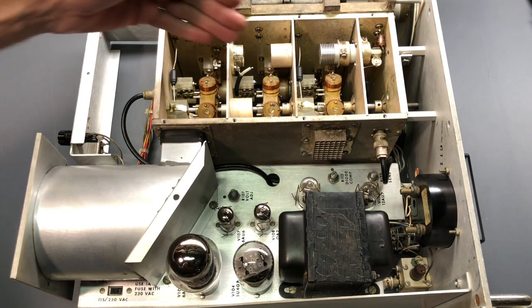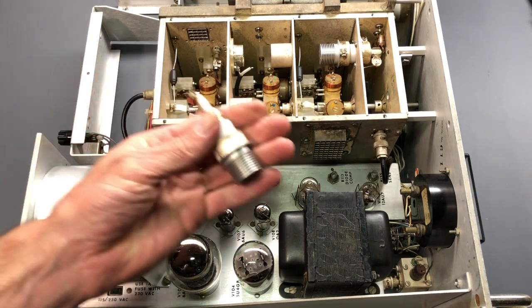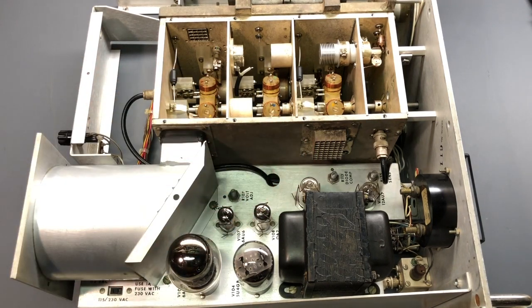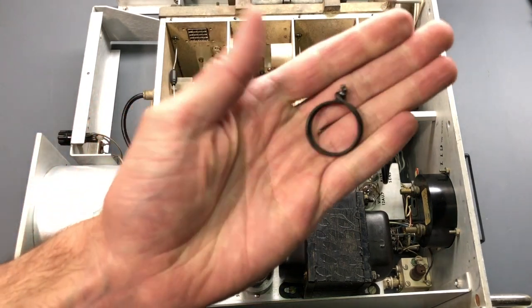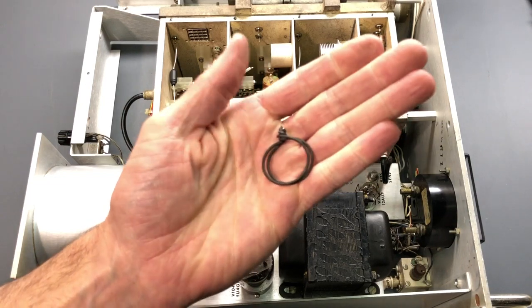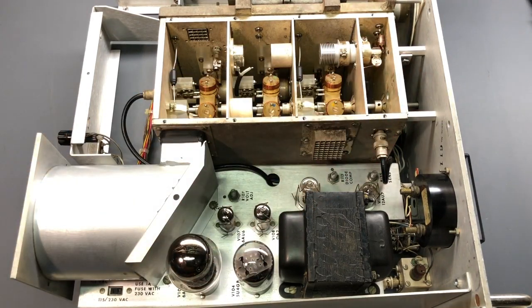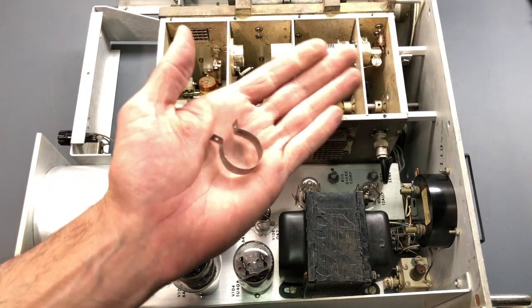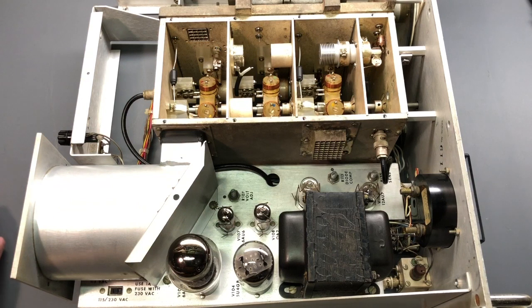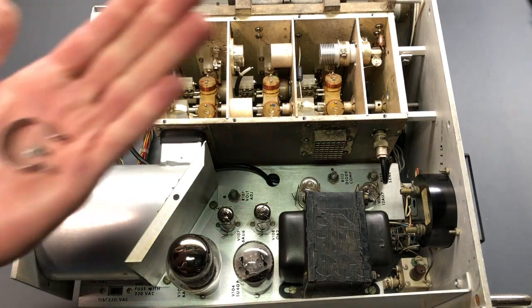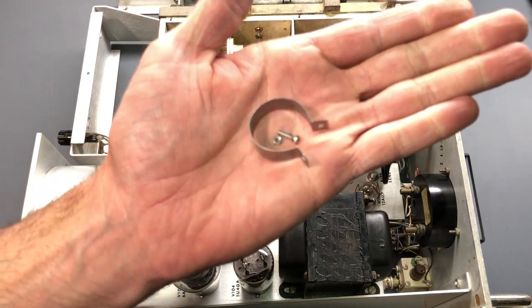Alright, you'll notice that a vacuum tube is missing right here. That tube has been removed, and I'll explain what's going on with this tube. So earlier in the video, you'll recall this makeshift clamp that someone had put in here. It was just this wire that had been wrapped around the holder for the tube. And I commented on that. It didn't look too secure and it would need to be replaced or taken care of. So of course I don't have the original clamp, and I couldn't find a clamp that was ready-made that would work. So I went ahead and made my own clamp right here. So it turned out really nice and should do the job. And a very small screw right here and nut like this. You can see there's the hardware to hold everything together.